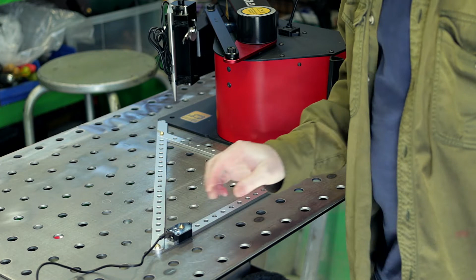He mentioned that he thought some of the problems were being generated because in the calibration routine, there is a set leeway parameter for the machine to move along and measure and capture those values. As it's measuring, if it gets a value that's outside of that leeway zone, it will not capture them, even though you can see the switch triggering on the screen.